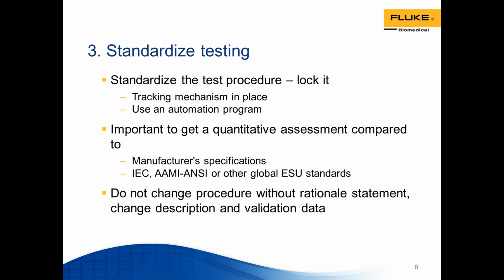In fact, it's important when you consider traceability and the unbroken chain of traceability of the medical device, which has been tested by the test tool that you're using, the test instrument, which is traceable all the way back to SI. That's the traceability path. And it's important to understand, therefore, whether the measurement that you're making is in or out of specification.